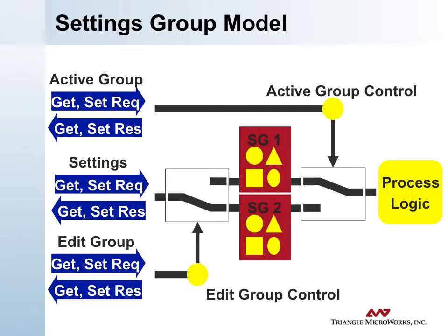This icon view of the settings group model shows how this process works. There's a control that you can do a get or set on — the active group control — that switches the process logic from one bank of values to another. At any given point in time, you can also set the edit group, which switches which group is available for editing, and then you can do get and set requests on the editable group to modify the values for the next time.